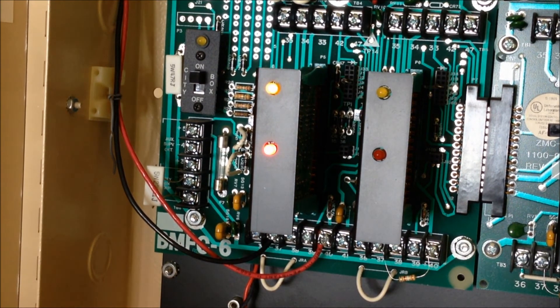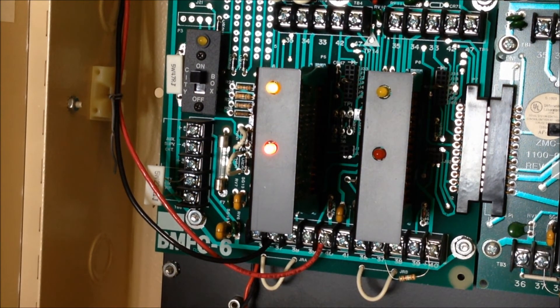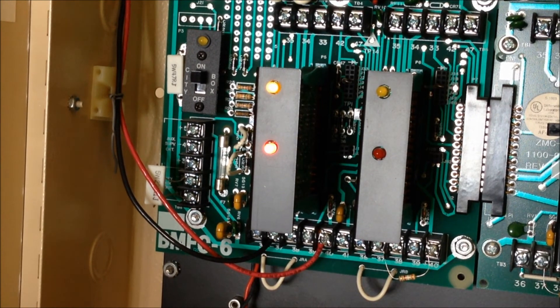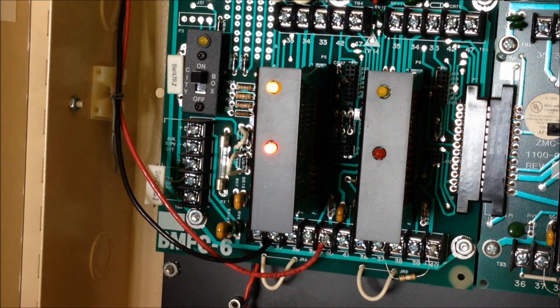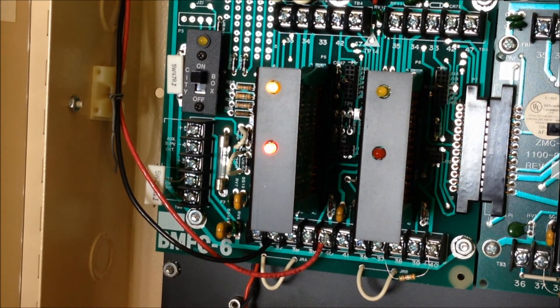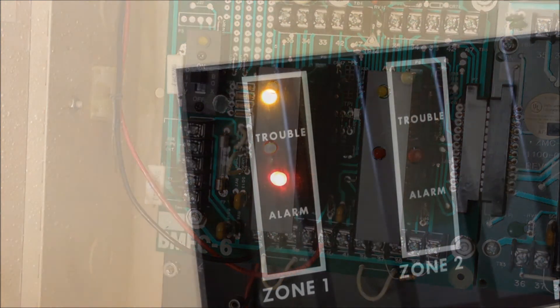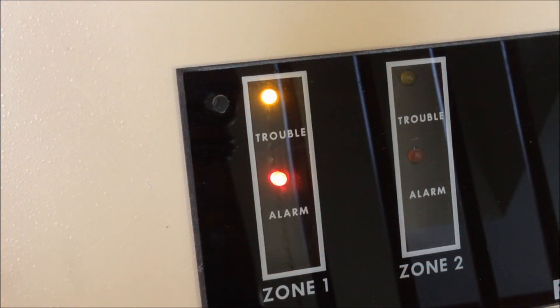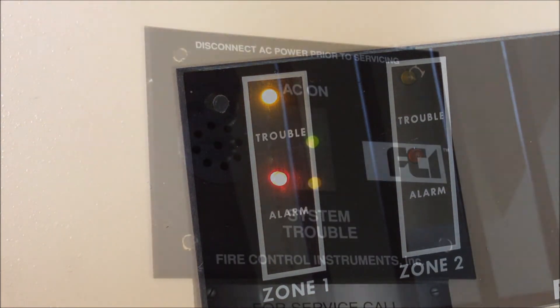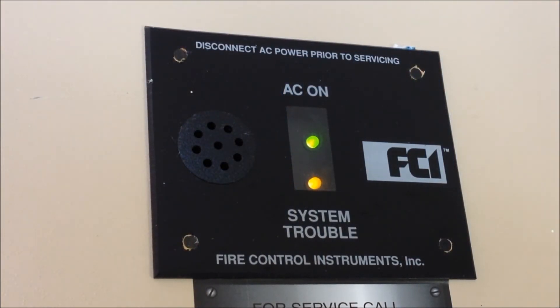So now the alarm is silenced and that does create a trouble condition on the panel so I'm going to go ahead and silence that as well. So now we have both the trouble and alarm indicators lit for zone one in addition to a system trouble indication up on the main display window.